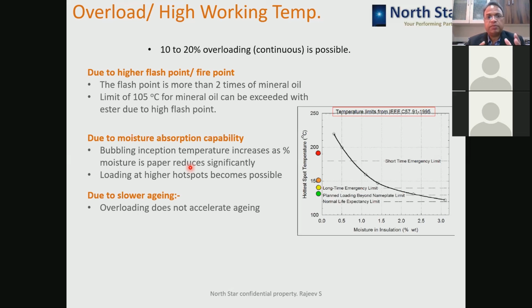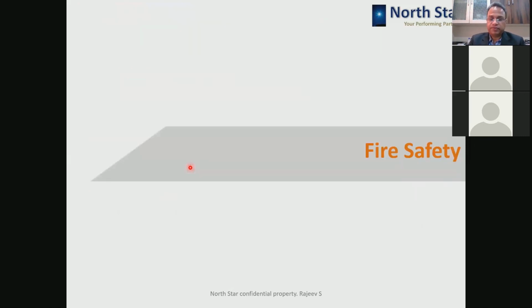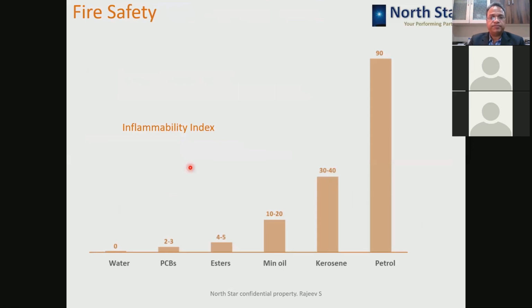So these three properties are helping you in overloading the transformer with natural and synthetic esters. Now let us talk about fire safety. This is the inflammability index of different systems. Water is fireproof, so its inflammability index is 0. PCBs is between 2 to 3. Esters 4 to 5. Mineral oil 10 to 20. Kerosene 30 to 40, and petrol, which is the most inflammable material, has 90 inflammability index.